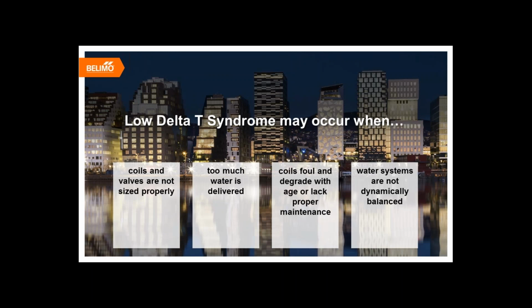Low delta T syndrome can occur in buildings for several reasons, 4 of which are: coils and valves are not sized properly, too much water is delivered to the coil or the heat exchanger, coils foul and degrade with age or lack of proper maintenance, and water systems usually are not dynamically balanced.